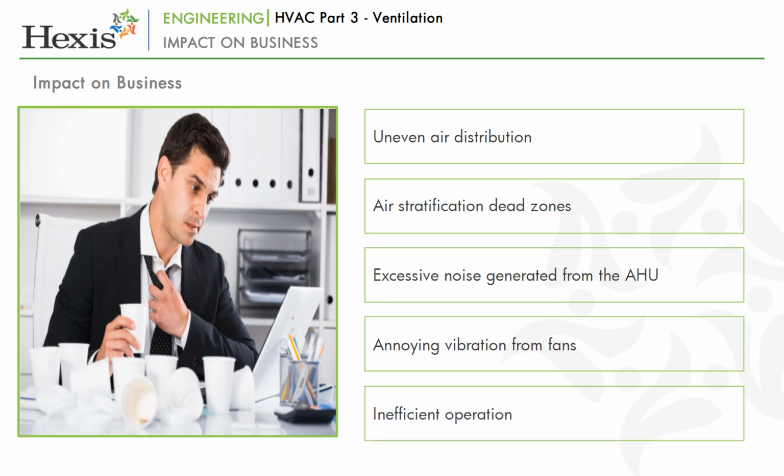It should also be remembered that at most facilities there is no redundancy built into AHUs and hence if one fails, the area being served will be severely impacted. Even where multiple units on same floor are there, failure of one unit will lead to overall drop of efficiency in all units.